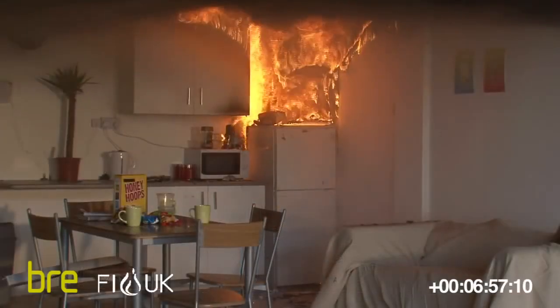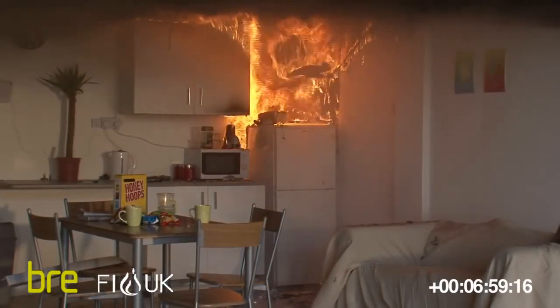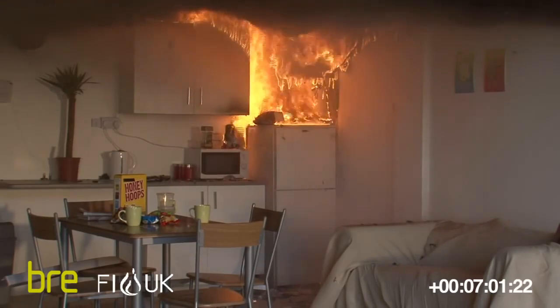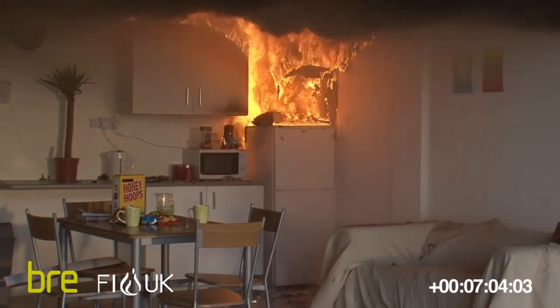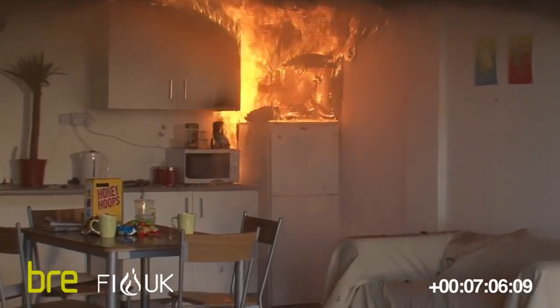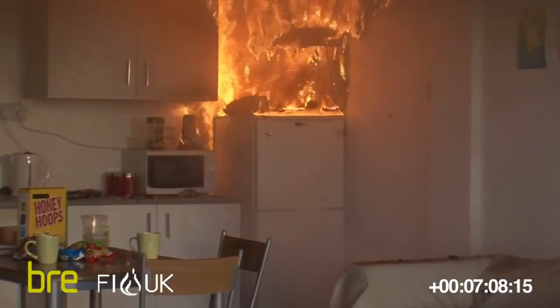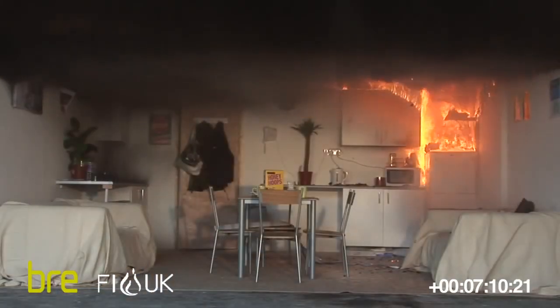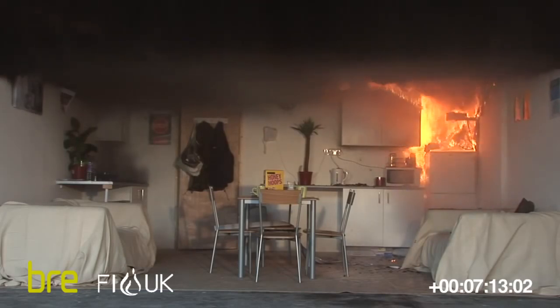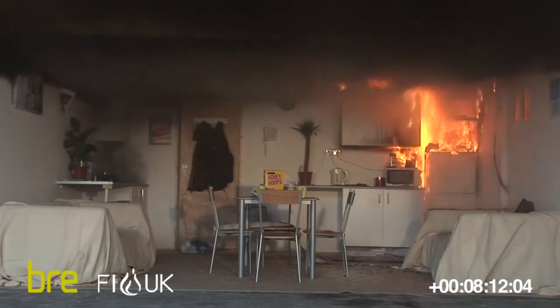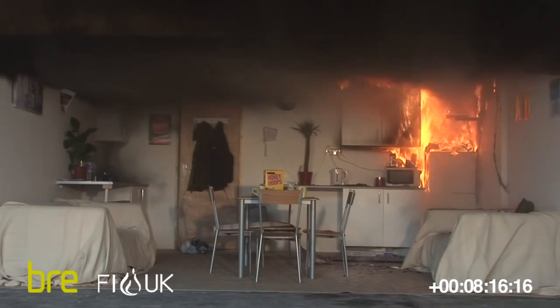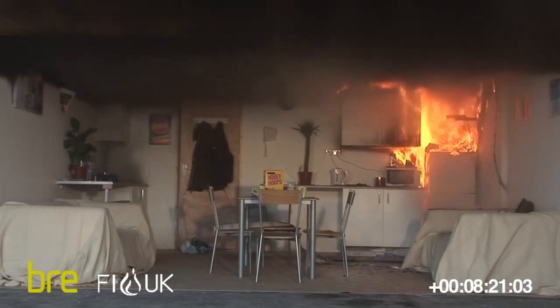Top surfaces of the sofa on the right, you can see it's starting to pyrolyse. So those are volatiles produced by the amount of heat that's being radiated down from the hot smoke layer, causing that pyrolysis to occur. We've got burning over the top of this cupboard and underneath it to the right. So as the fire continues to grow, all that process of recycling heat going up into the hot smoke layer and then being radiated back down onto the fuel below, all of that is increasing and recycling back, causing further increase in the fire size.